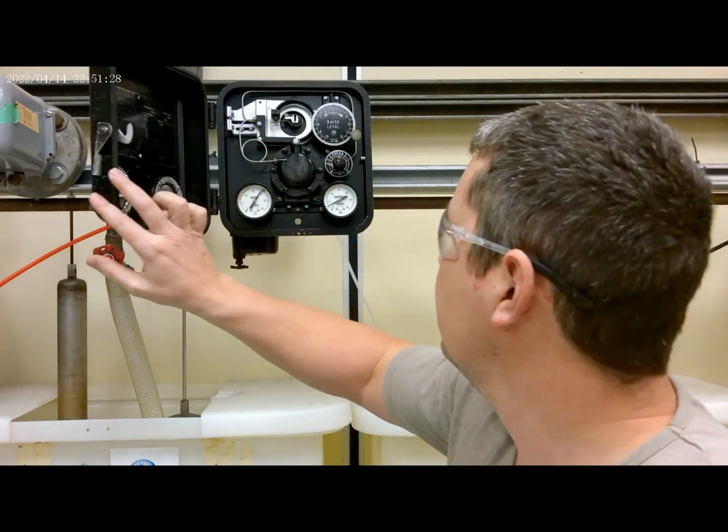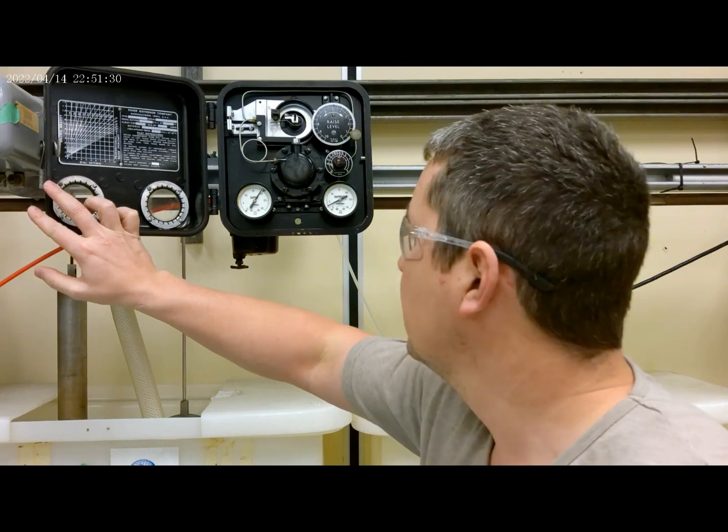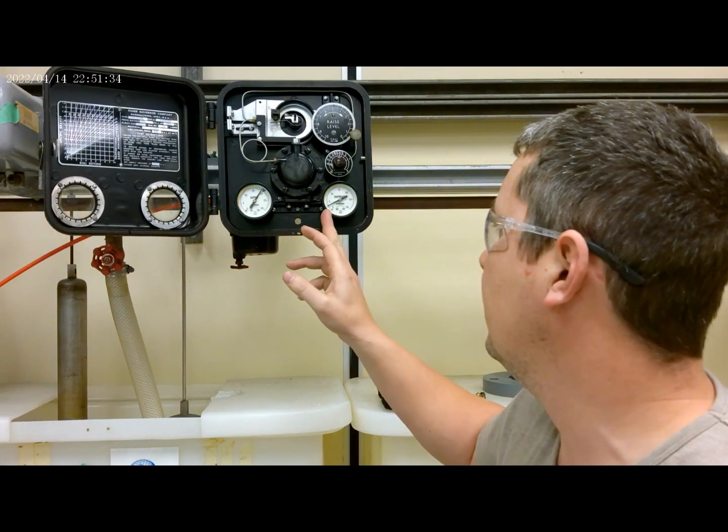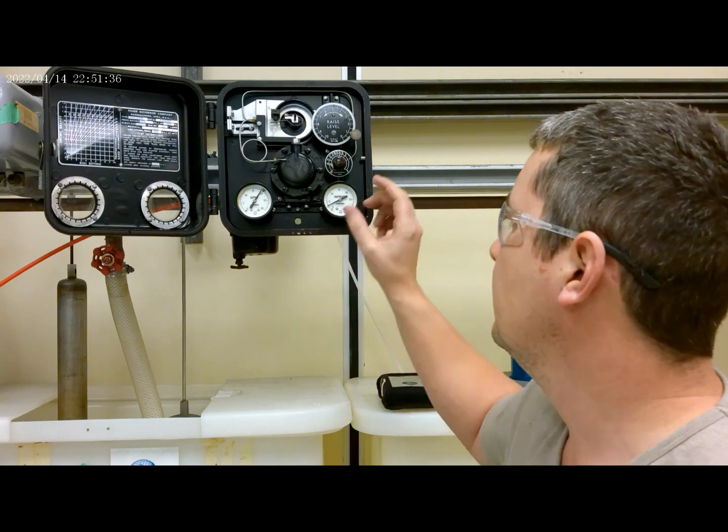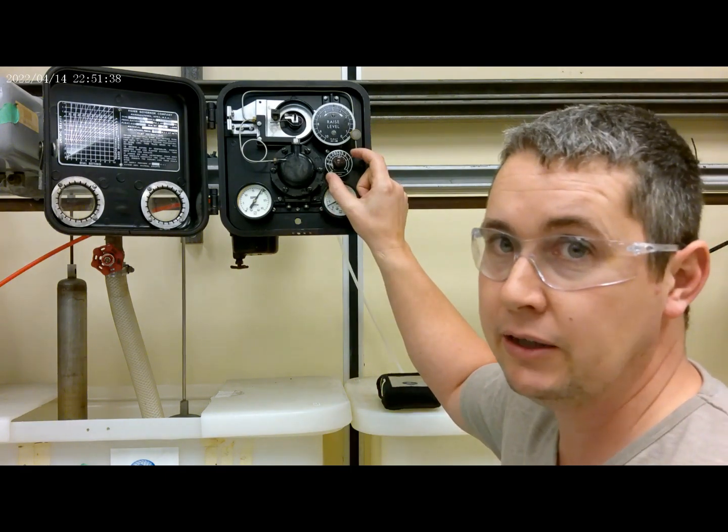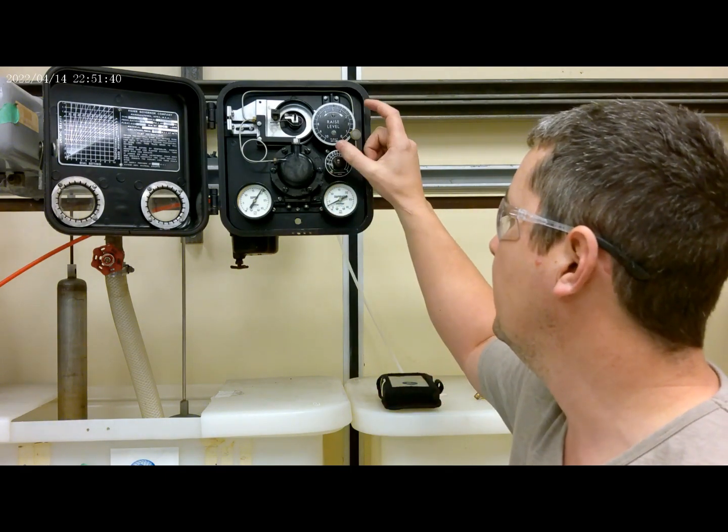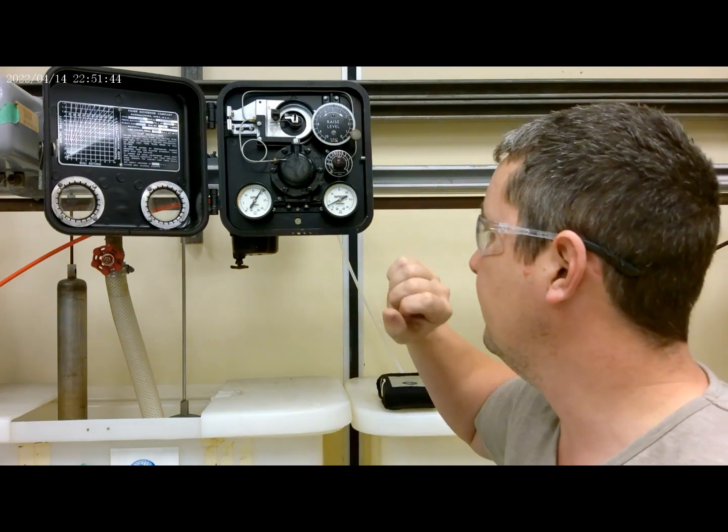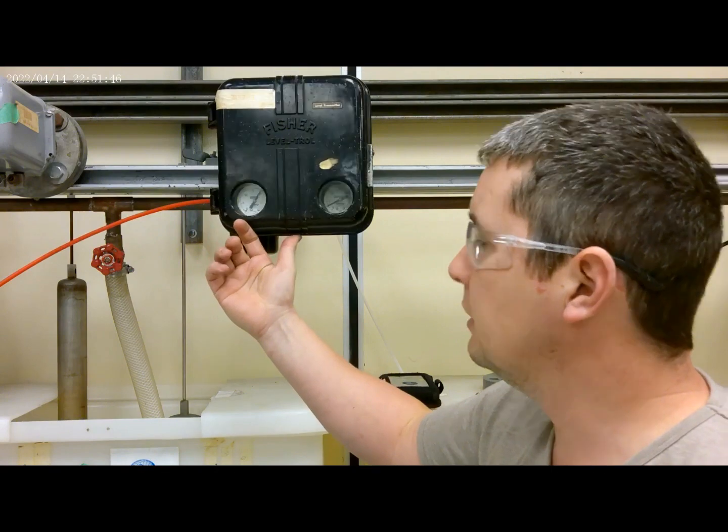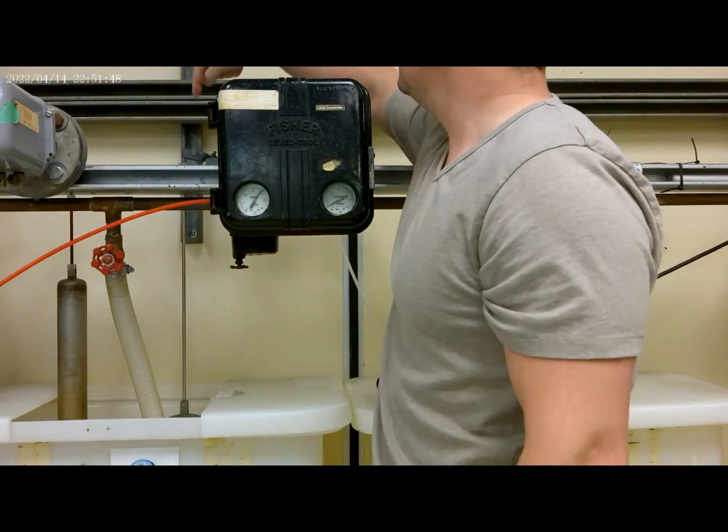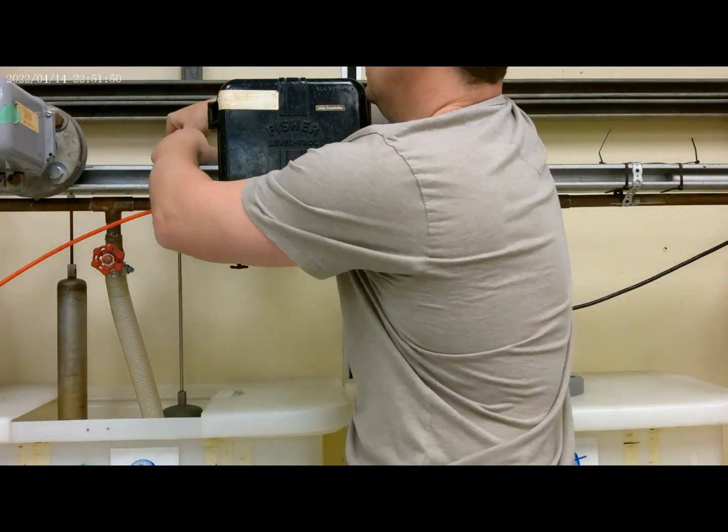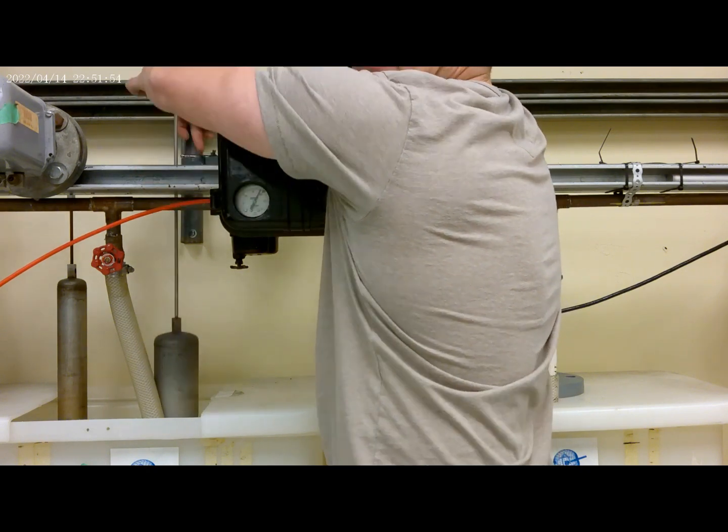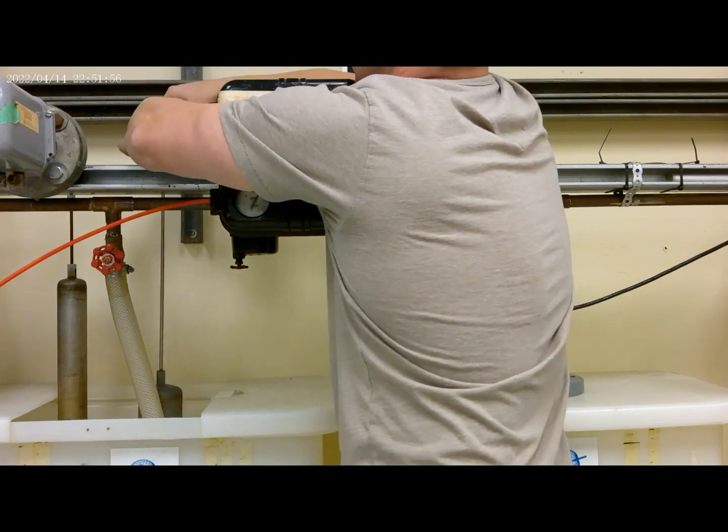Now here we have the inside of the controller. We have the supply pressure is just about 20 psi, and our output currently is 3. We have our proportional band setting here, and we have our position, our zero level right here. Be sure that on these we always make sure that this is not pinned, so that it's not stuck up here.